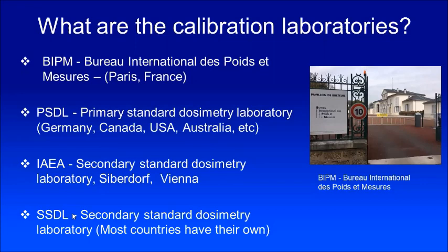What is the difference between the primary standard dosimetry laboratory and the secondary standard dosimetry laboratory? A primary standard dosimetry laboratory has measurement techniques where they can directly provide you the absolute dose. Whereas a secondary standard dosimetry laboratory has an ion chamber or dosimeter that requires a calibration — they don't directly get absolute dose, but they have a calibration factor from a primary standard dosimetry laboratory.